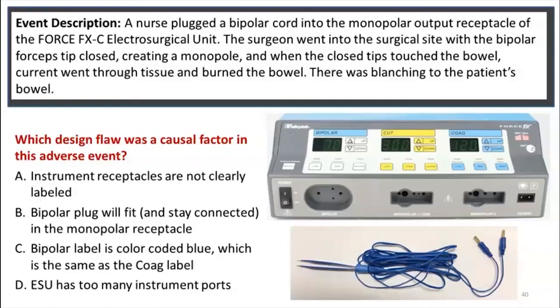I also would agree that the bipolar label should probably be color-coded to match its buttons, in this case white, but again, don't expect that this change would prevent the adverse event. On the other hand, if the bipolar plug was unable to fit into the monopolar receptacle, this adverse event would not have occurred.